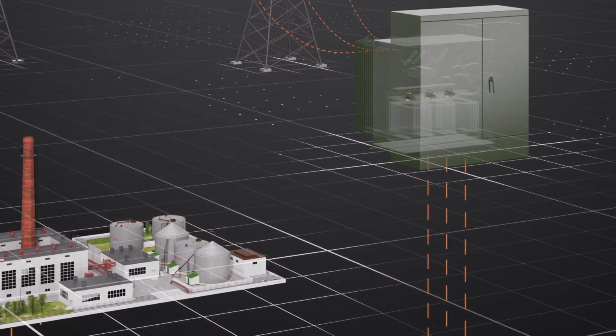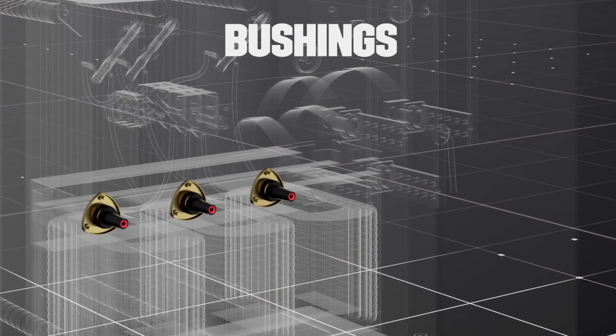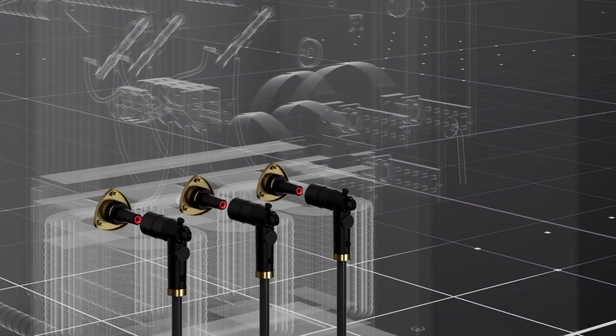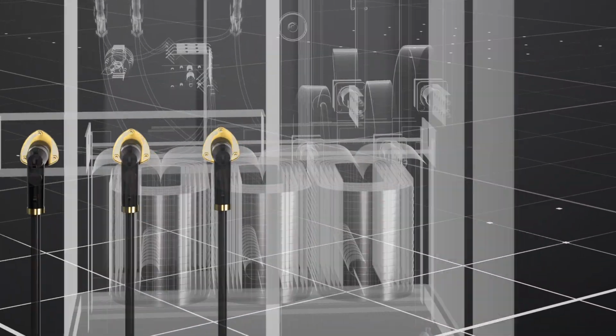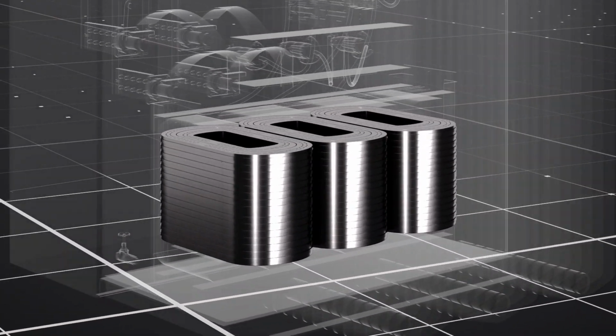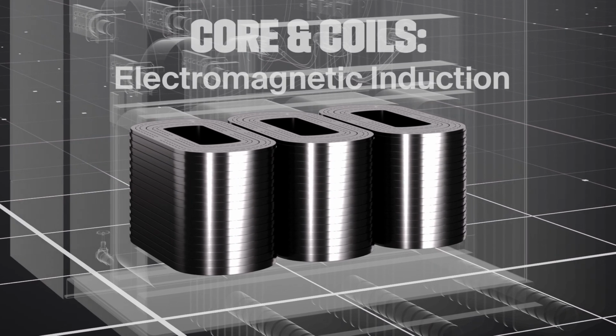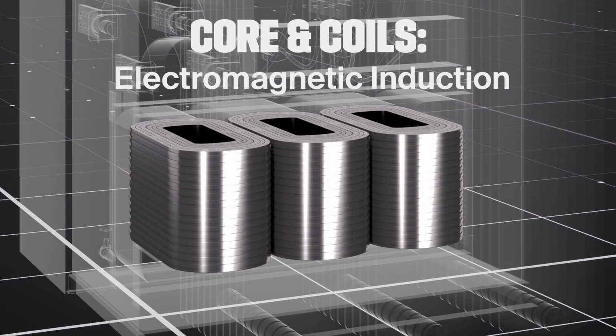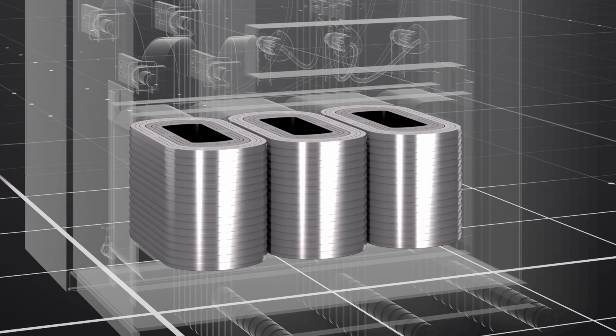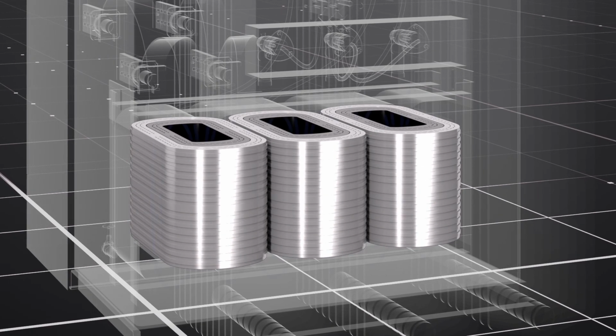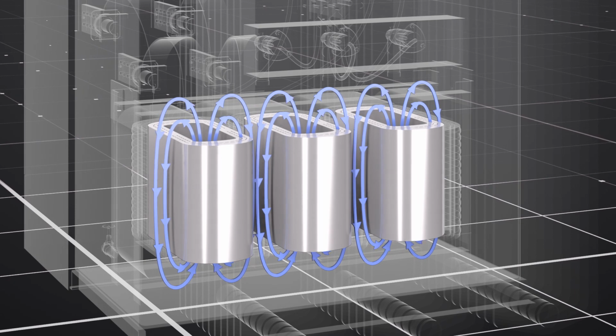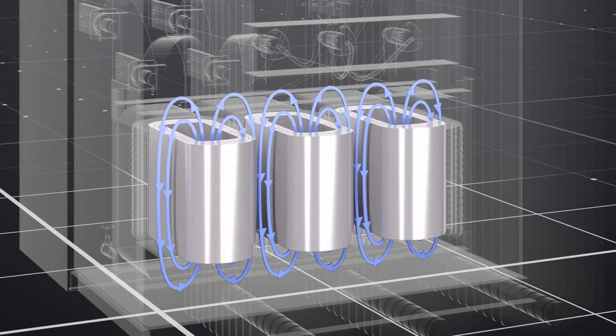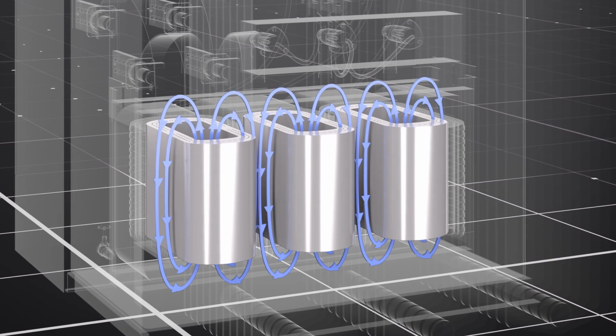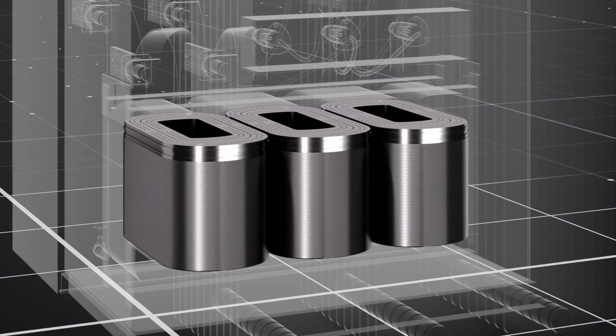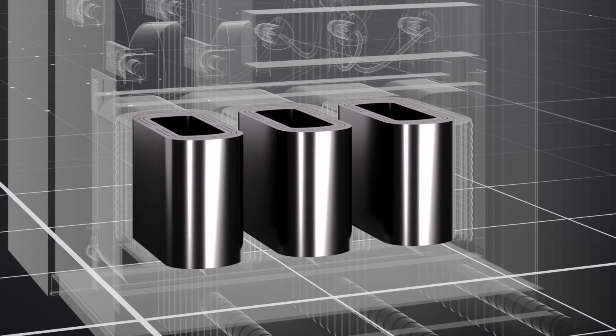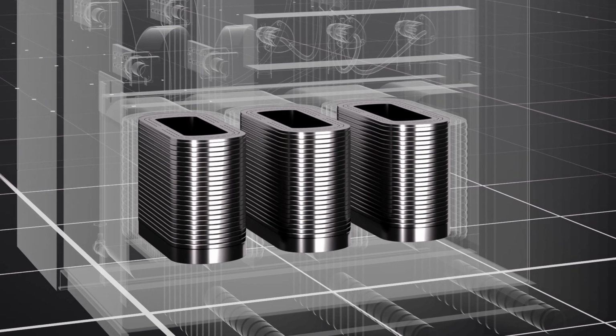Let's take a closer look at how it works. High voltage bushings connect the transformer to the power source. The core and coils are the heart of the transformer. Current flows from the power source into the primary coils. The current flowing through the coils generates a strong magnetic field, which induces a current into the second set of coils located inside the first. This process is called induction. The ratio of loops in the primary coil to that of the secondary coil is what determines the voltage the transformer converts the power to.